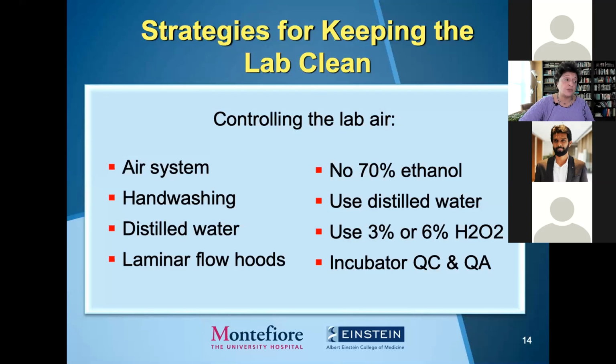Only distilled water should be used routinely with a lint-free wipe to clean surfaces of hoods, counters, and heating stages. For decontamination of surfaces, including the hood between oocyte retrievals and after the last retrieval, use 6% hydrogen peroxide on a lint-free wipe followed by a rinse with distilled water. One can also use 3% hydrogen peroxide or other low VOC cleansers on your walls and on the floors of the lab. Incubators today are largely benchtop, either dry incubation or with a small water reservoir providing humidified culture conditions. Incubator QC and QA usually follows manufacturer's recommendations.